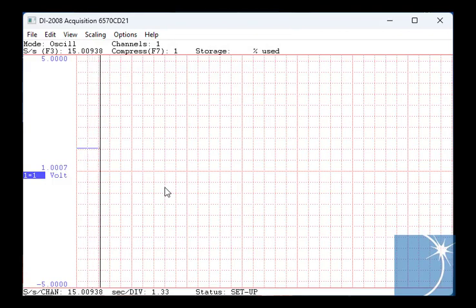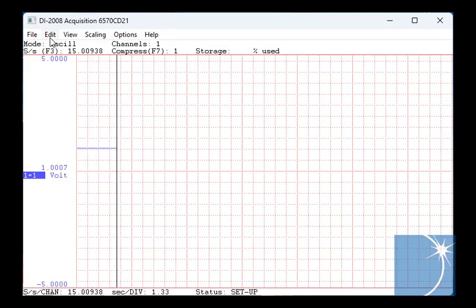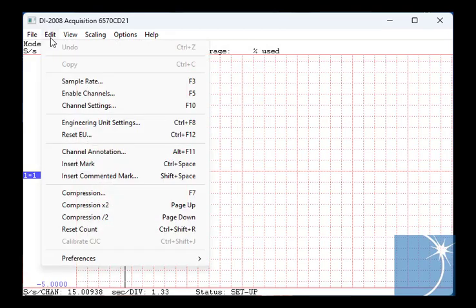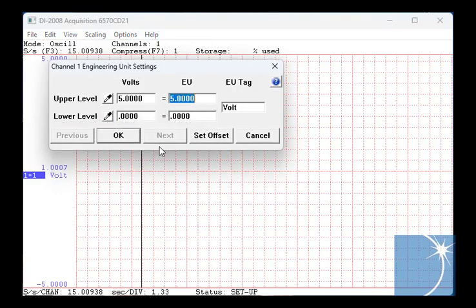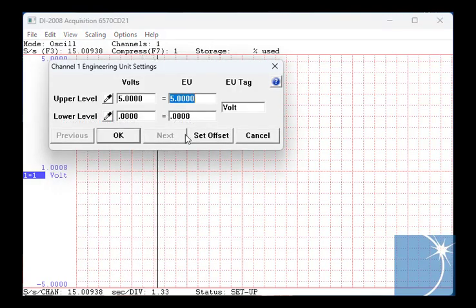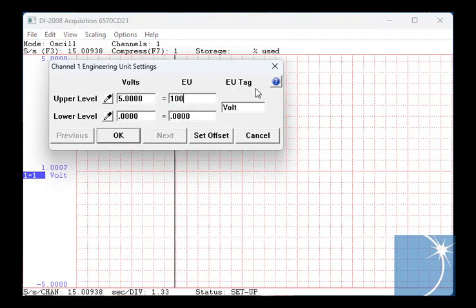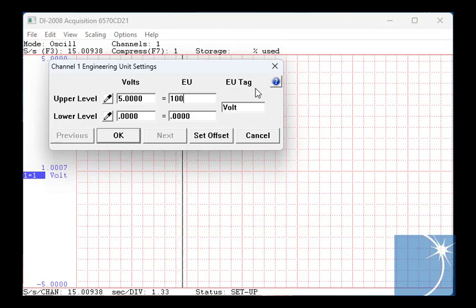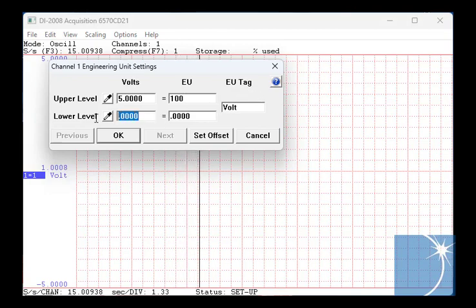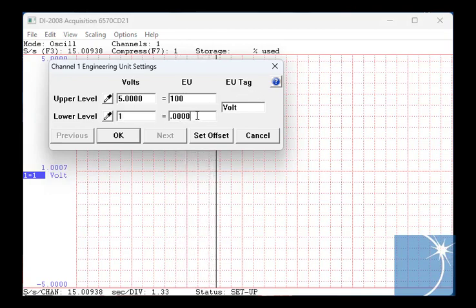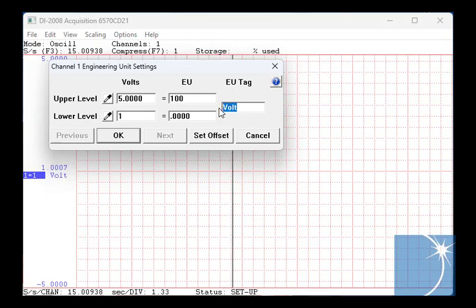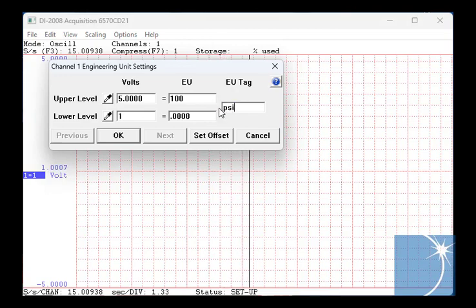Next we'll scale the 1 to 5 volts signal into meaningful units, in this case PSI. To do so, we'll select engineering unit settings from the edit pull down menu. We'll set 5 volts equal to 100 and 1 volt equal to 0 and change the EU tag to PSI.